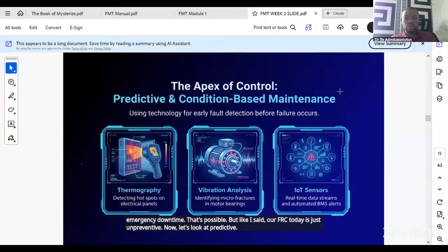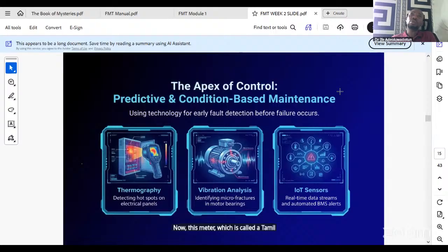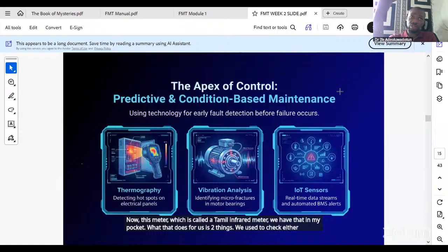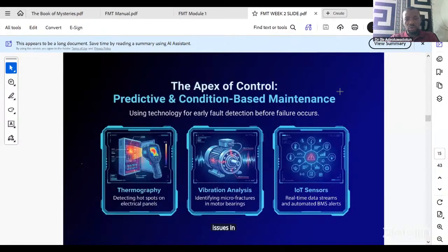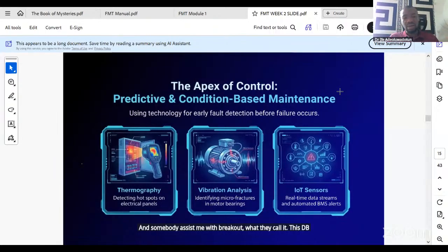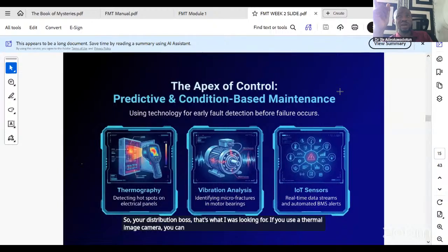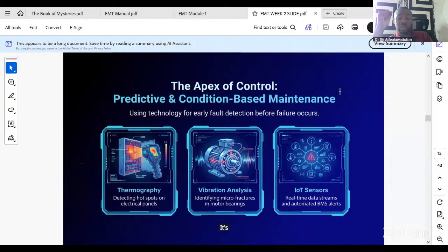I'm just touching on this. This meter, called a thermal infrared meter, I have one in my pocket. What it does for us is two things. We use it to check for issues in what they call the DB - your distribution box. If you use a thermal image camera, you can know which breaker will have an issue - the one already showing unusual heat - you scan that location.